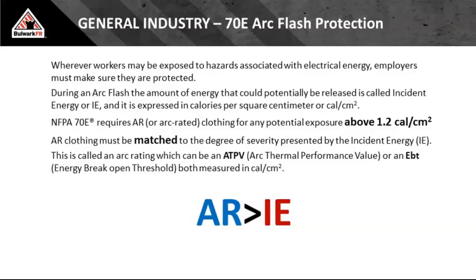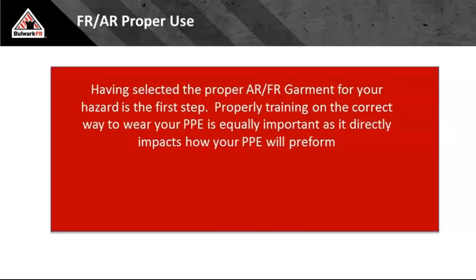But remember, rubbers and leathers are very insulative to the heat coming out in incident energy. In many cases, you have 30, 40, 50 calories of protection between your rubbers and leathers that you're utilizing when you're working on energized equipment. So if you're deploying all your PPE, that's going to be beneficial than not.